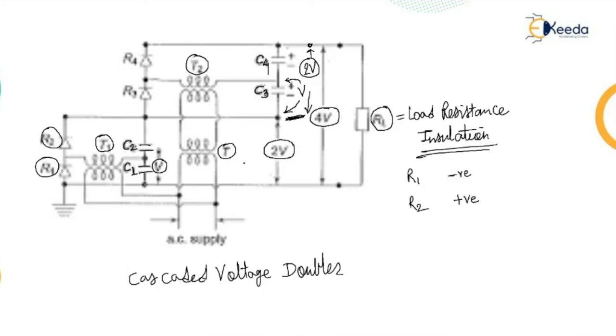The arrangement may be extended to give even 6Vmax, 8Vmax and so on by repeating further stages with suitable isolating transformers in all the voltage doubler circuits. If valves are used, the filament transformers have to be suitably designed and insulated, as all the cathodes will not be at the same potential from ground. The arrangement becomes cumbersome if more than 4Vmax is needed with the cascaded steps.